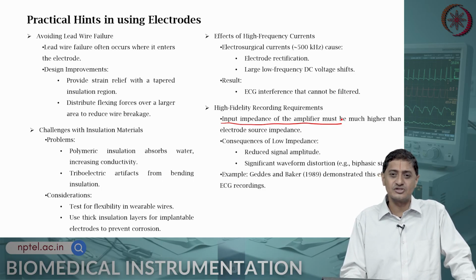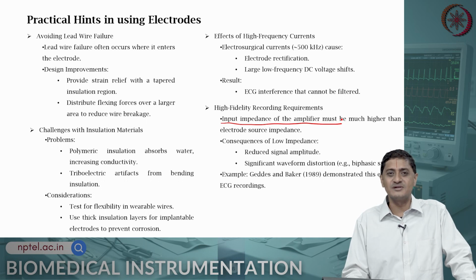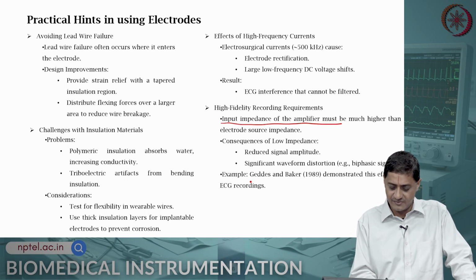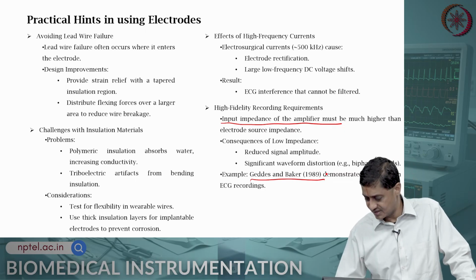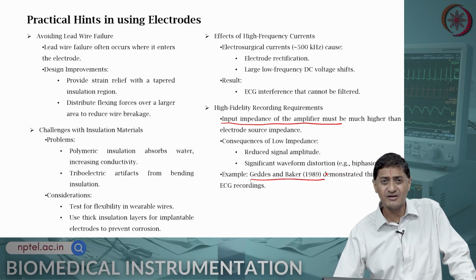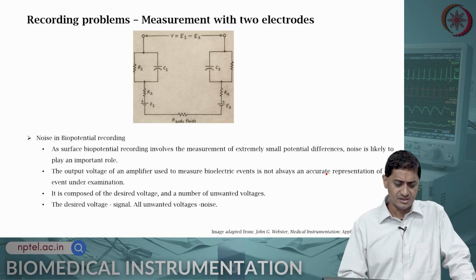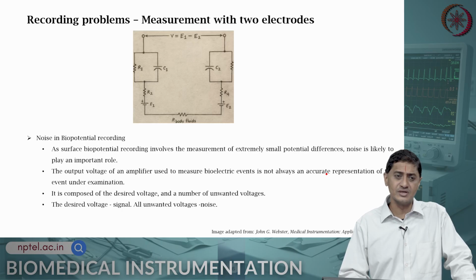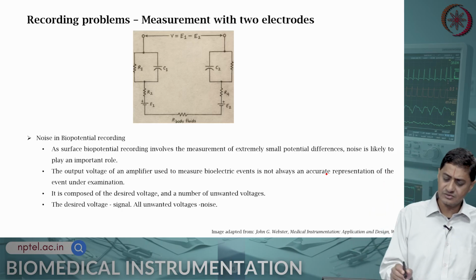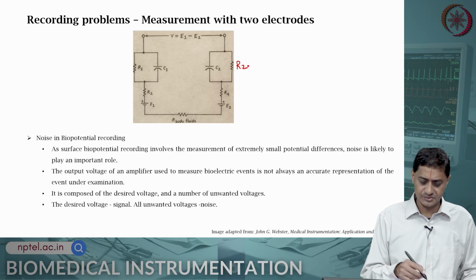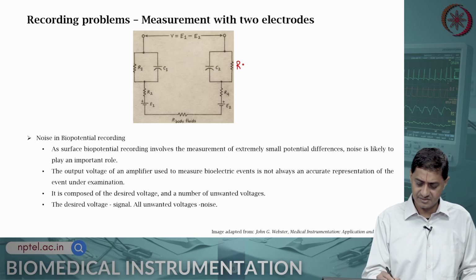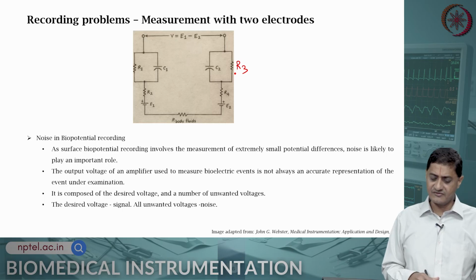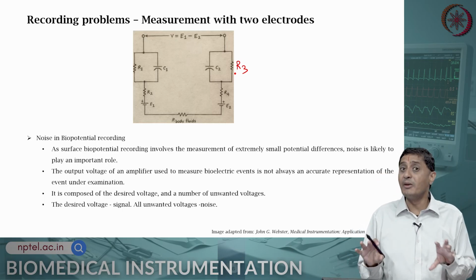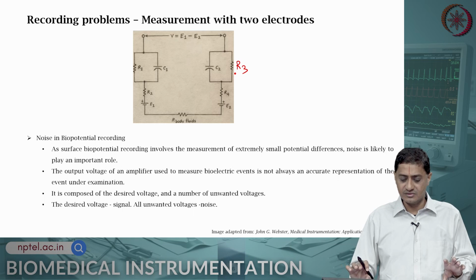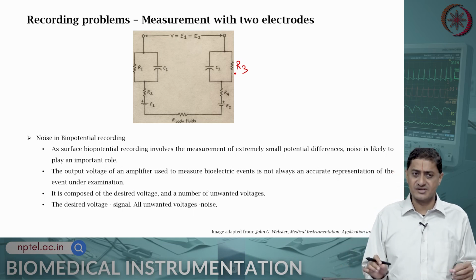Significant waveform distortion happens. For example, this effect has been demonstrated by Geddes and Baker in 1989 in ECG recordings. If you have low input impedance, what happens? For example, here is a measurement that I am doing with 2 electrodes. This is R2 C2, or R3 C2, whatever, and I have 2 electrodes. I am in a bipolar configuration. I am measuring say EMG, for example.